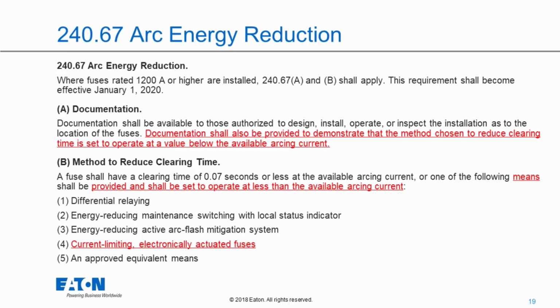So the first thing you look at is, well, if my fuse is 1,000 amps, do I have to worry about this condition? The answer is no. I do not have to worry about it. My fuse must be rated 1,200 amps or higher. Also notice the wording is a little bit different than NEC 230.95 for ground fault protection of equipment, where it refers more to the switch size. So per 230.95, it says where the largest ampacity of the fuse could be installed. So if you had a 1,000 amp fuse and a 1,200 amp disconnect switch, you would have the requirement to meet the requirements for GFPE. However, you would not have to meet the requirement for 240.67.